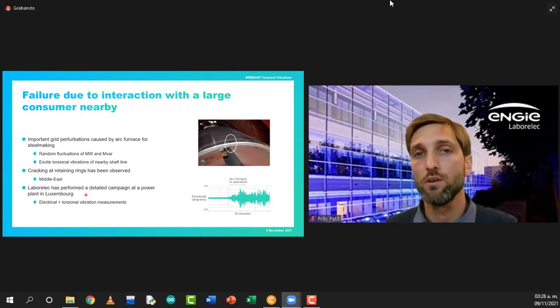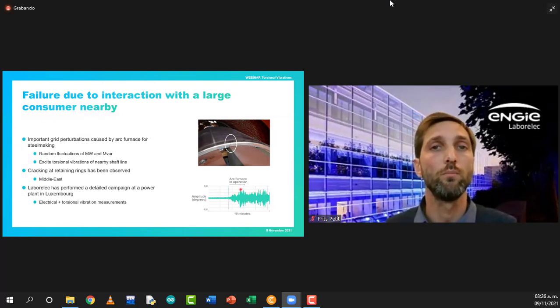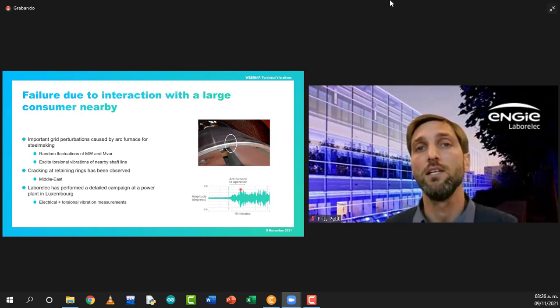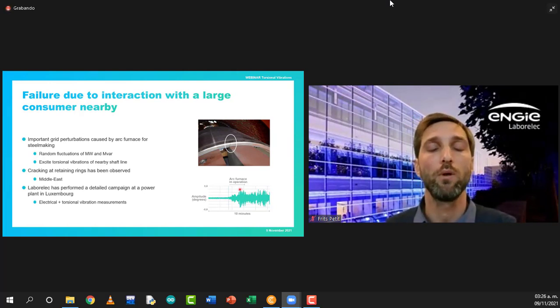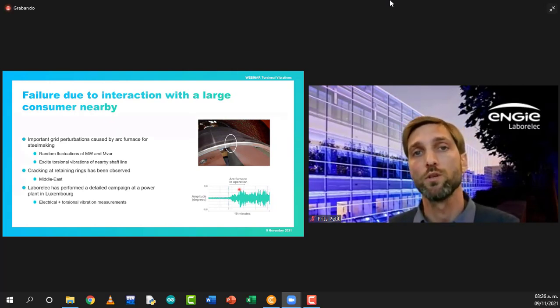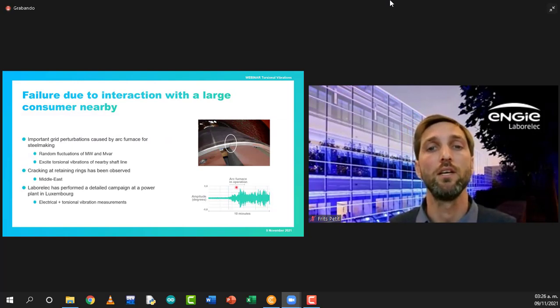We performed a similar detailed campaign at a power plant in Luxembourg, where we did both electrical and torsional vibration measurements and, as well, revealed clearly the impact of the arc furnace. When the arc furnace was put into operation, there was a clear increase in the torsional vibration, and the analysis then led to a mitigation action, meaning that the electrical route in between the power plant and the arc furnace was changed. So it was made longer in order to mitigate the interaction.